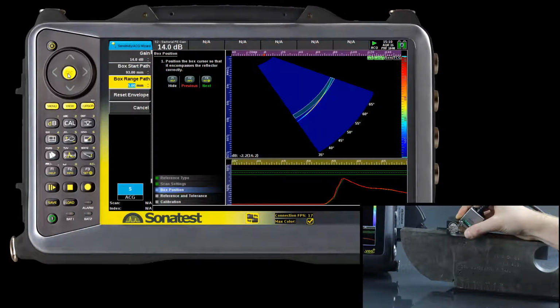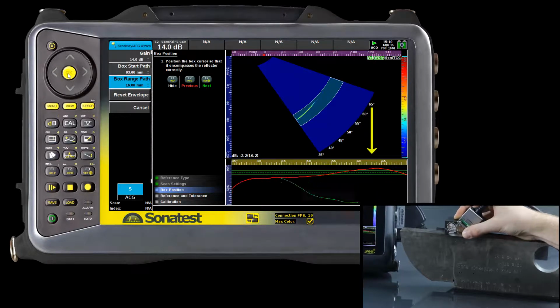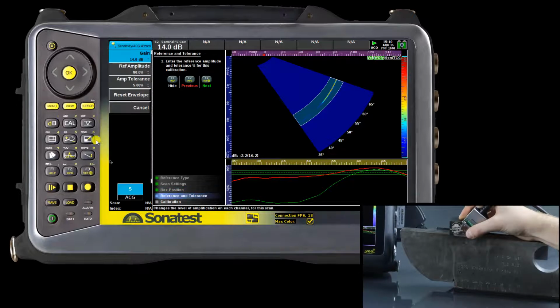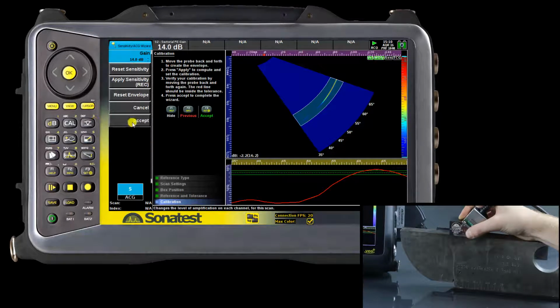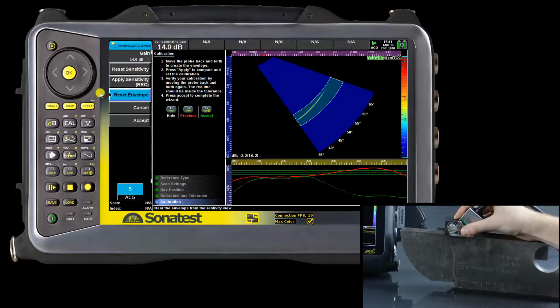Once the radius has been swept completely, we can easily see that some angles have higher responses than others. The reference is set at 80% and the tolerance at 5%, which is good because the signal response is already close to the value. Before recording the signal, or if a mistake occurs, we can reset the envelope before applying the sensitivity. Once the envelope has been recorded, we can apply the sensitivity gain correction to the signal. At this stage, we recommend you do a validation of the signal correction.